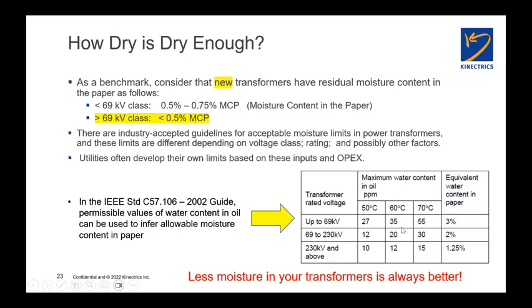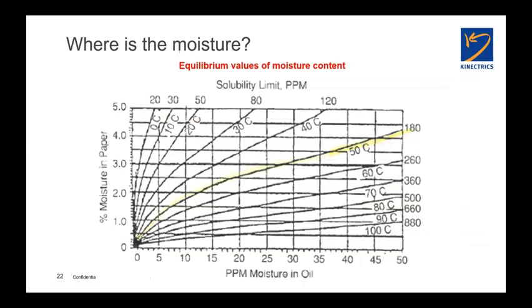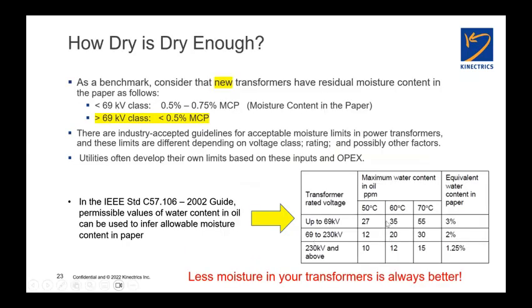We can back into some numbers, if you will, through IEEE C57.106, where it talks about permissible values of water content in the oil. So we could use our friend the Oommen curve and use the parts per million of the oil at a temperature and come up with associated moisture content in the paper. And you see some numbers here. A lot of utilities have developed, over the years, their own limits from their own engineering standards. So this is some guidance in the absence of that data.